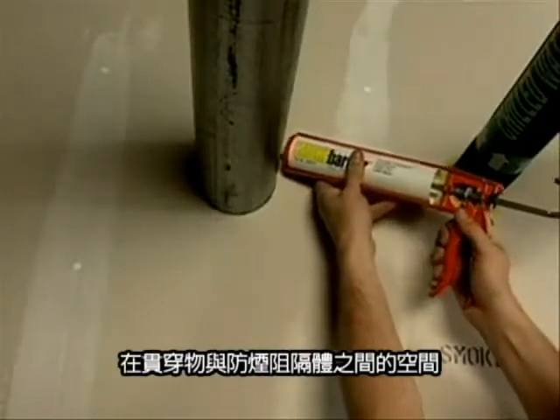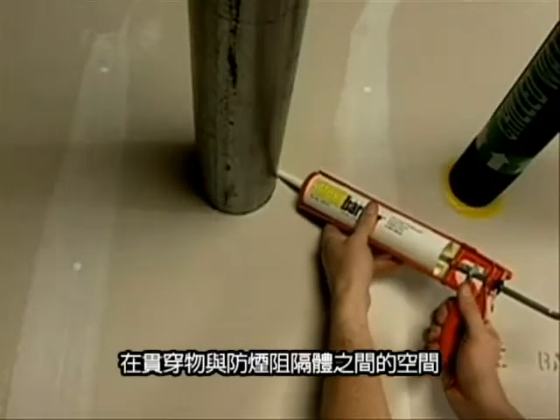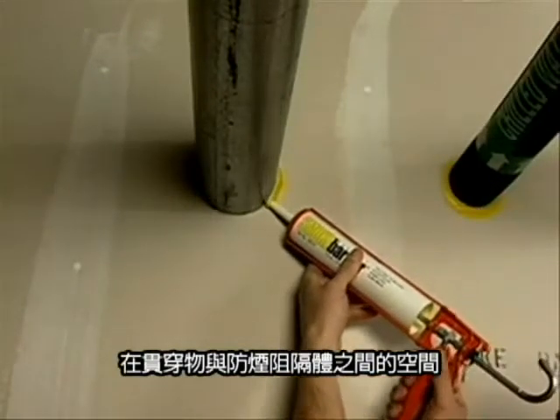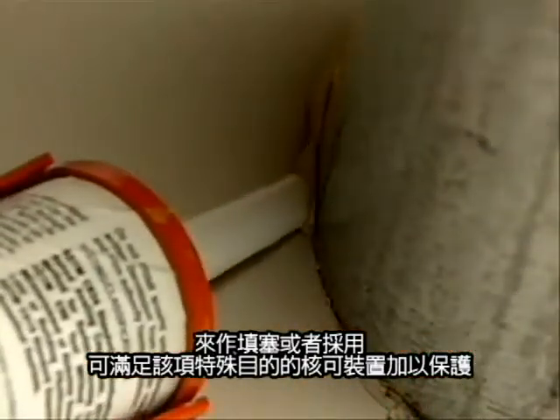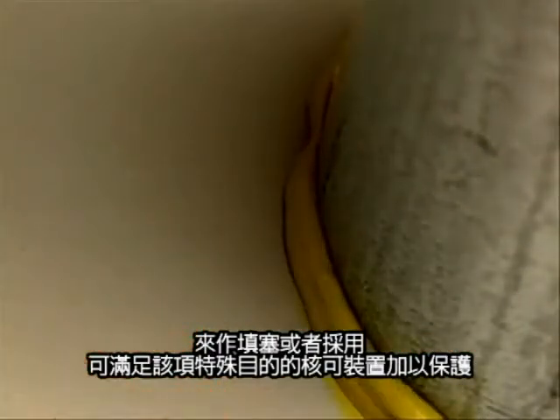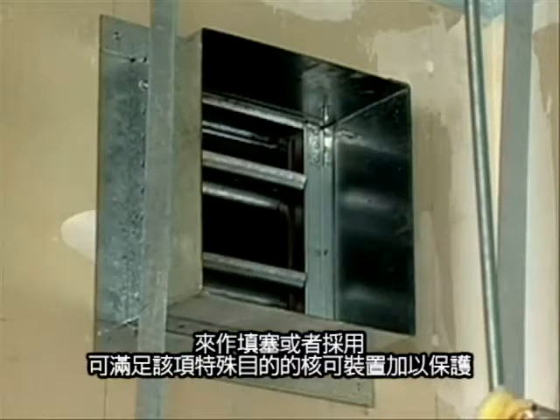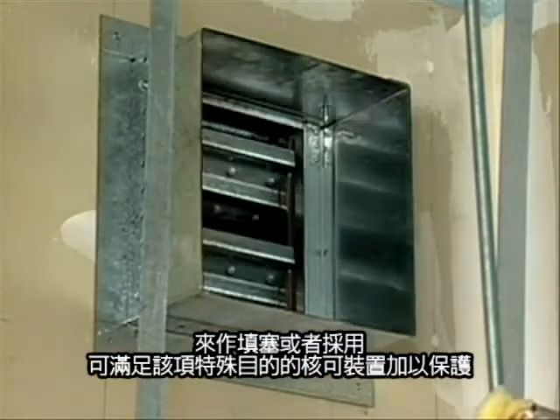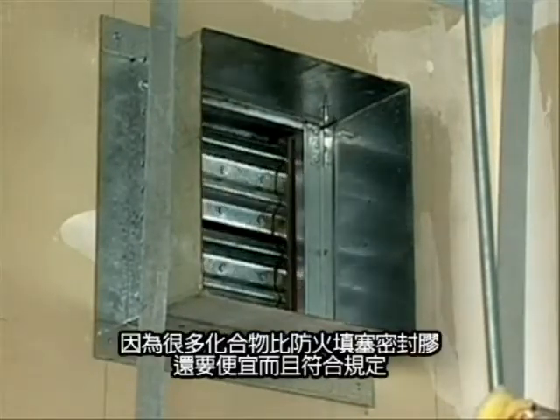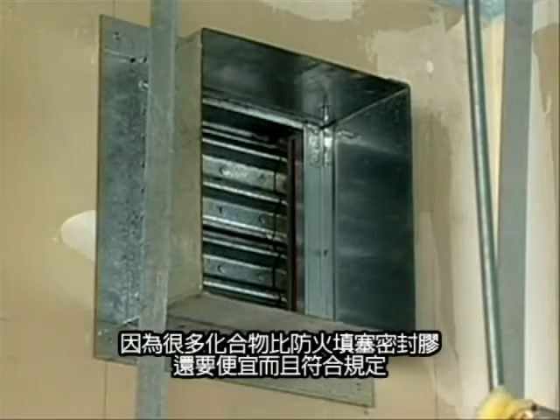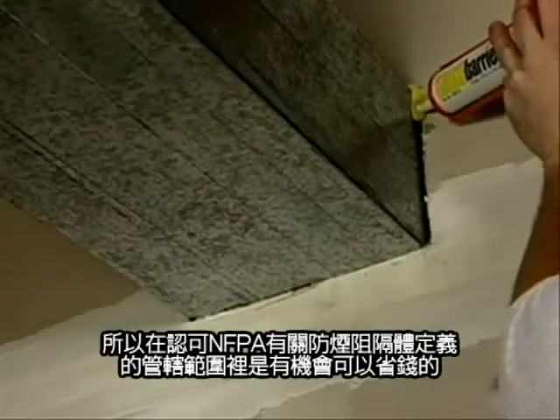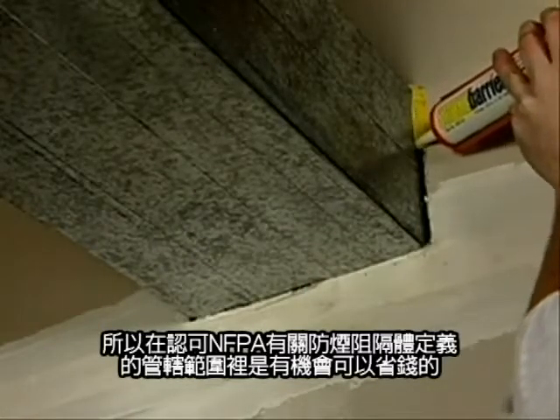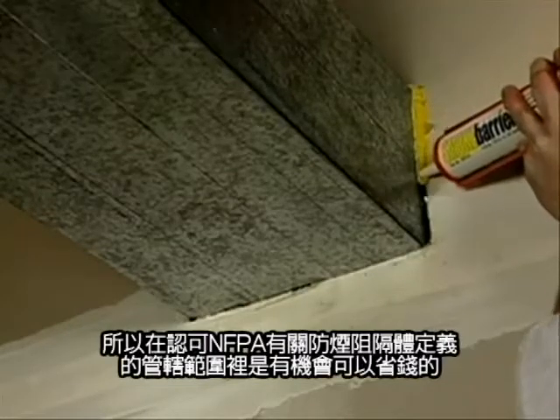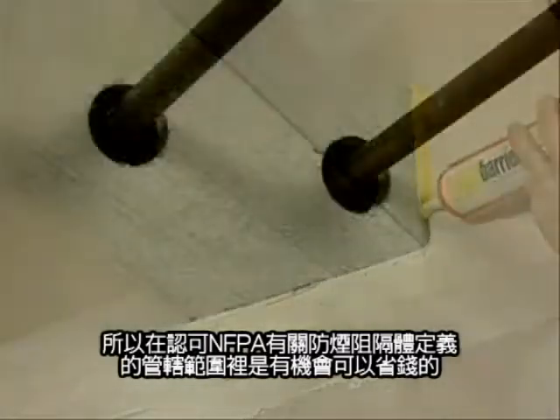The space between the penetrating item and the smoke barrier should be filled with material capable of maintaining the smoke resistance of the barrier or be protected by an approved device designed for that specific purpose. Because many compounds are less expensive than fire stop sealants and meet this requirement, there's an opportunity to save money in jurisdictions that recognize the NFPA definition of smoke barriers.